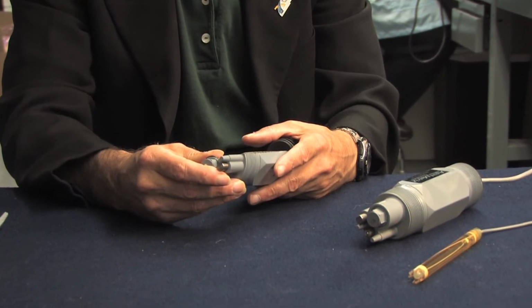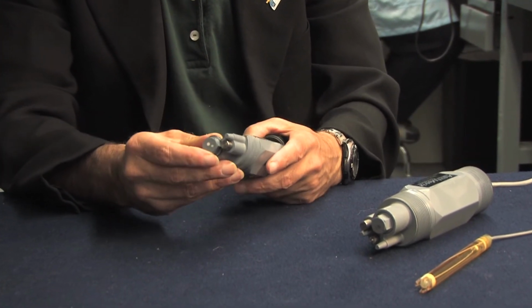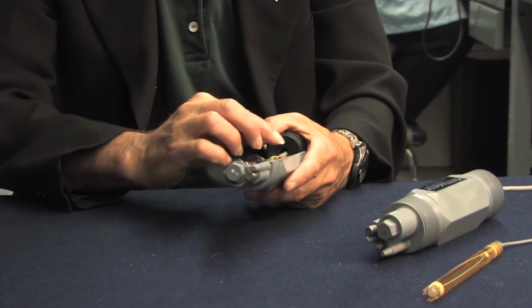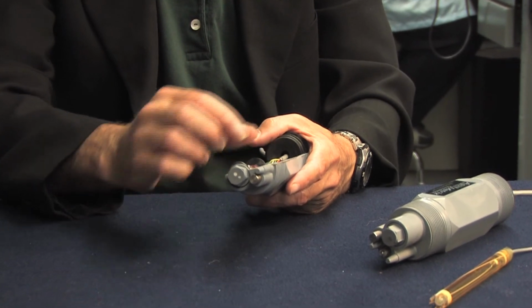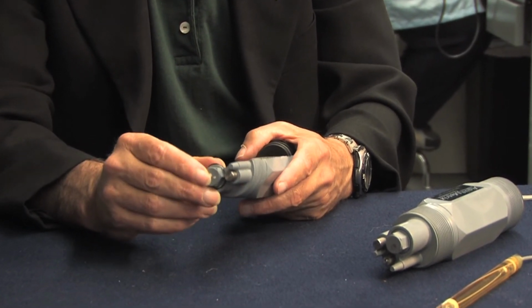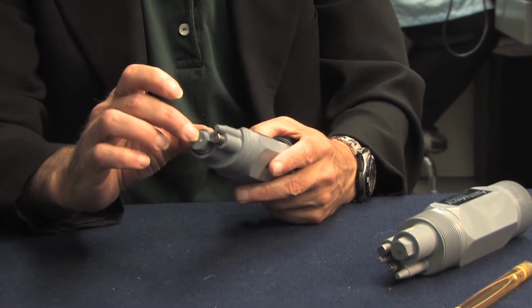The porous junction that linked the salt solution surrounding the silver wire in the combination probe is now a replaceable component that we call a salt bridge. It has a porous junction on both sides and is packed with concentrated potassium chloride. The ground rod also contains a temperature element so that the analyzer can correct the pH for the temperature. The little circuit board has a preamplifier that takes the low current signal and converts it to a high current signal. This arrangement has several advantages.